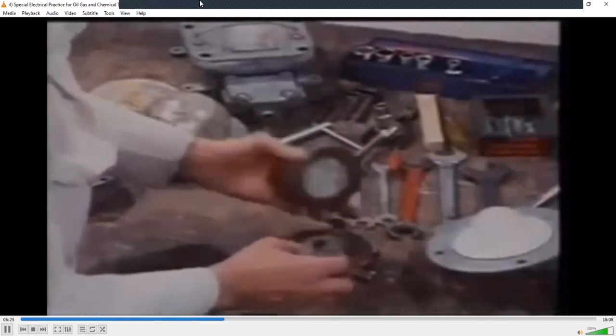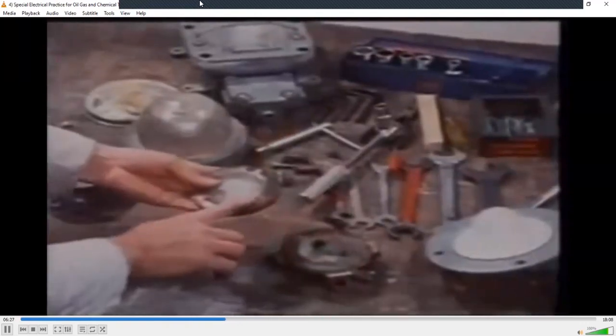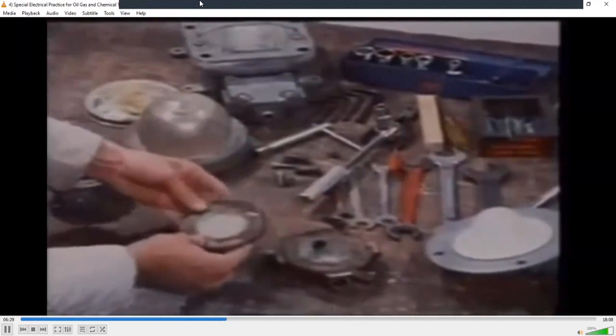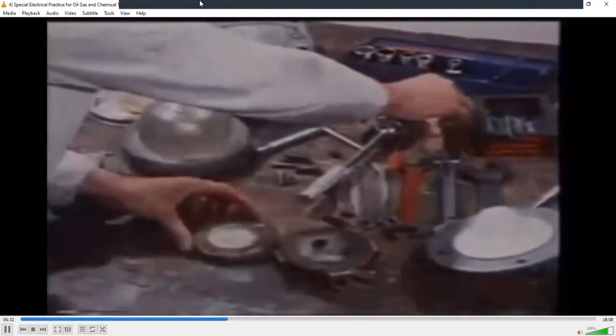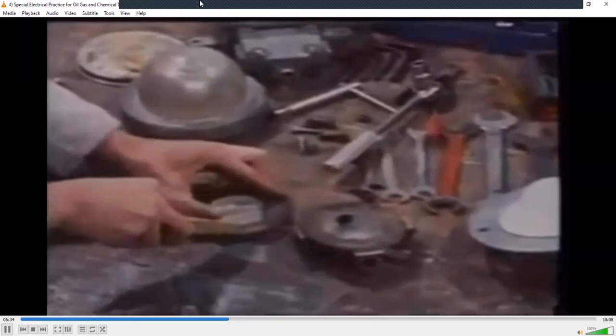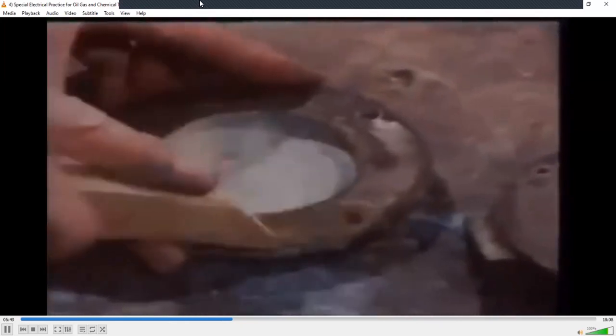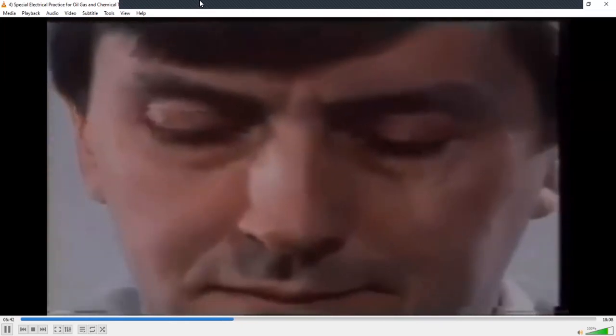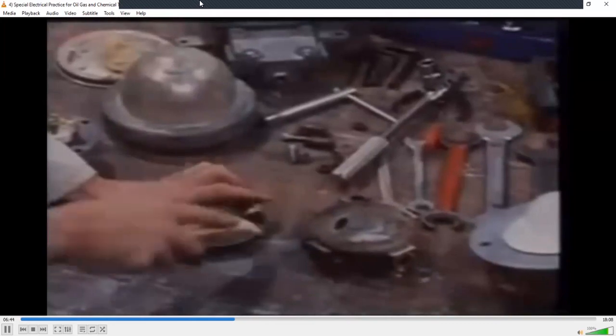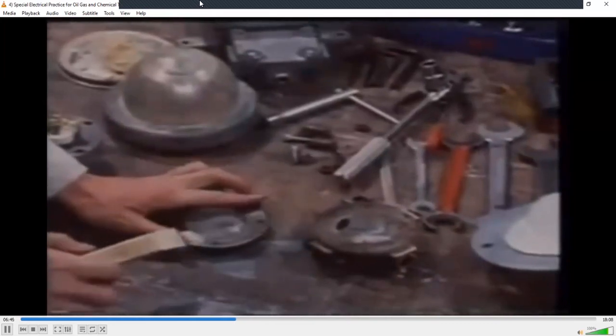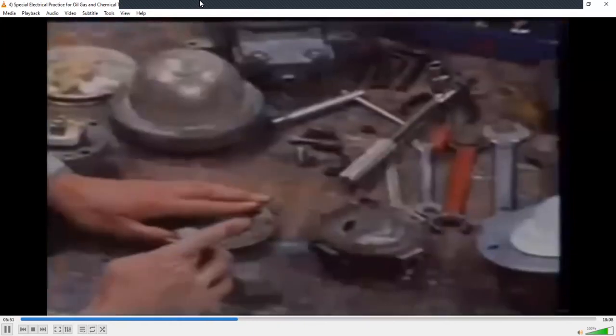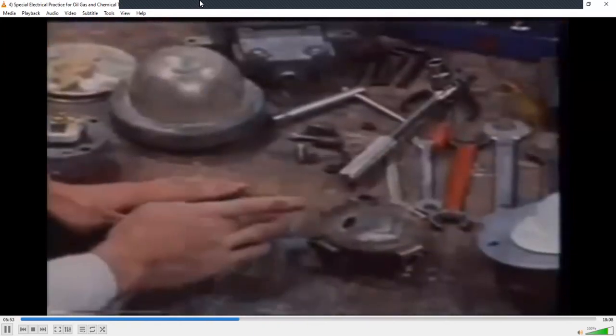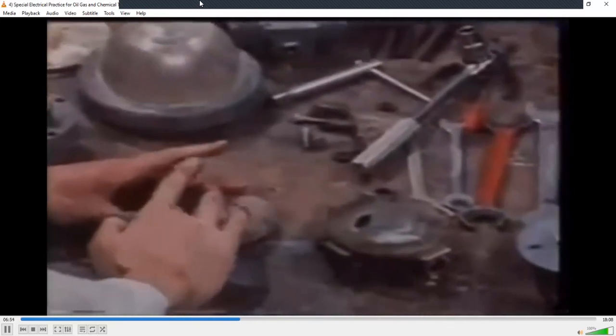The maintenance of a flame-proof light fitting involves 2 specific objectives. First, the prevention of any deterioration in the equipment's safety level, and second, ensuring its correct, safe function. Use only non-abrasive materials for cleaning. Lightly grease, then wipe clean the flanges before fitting them together.